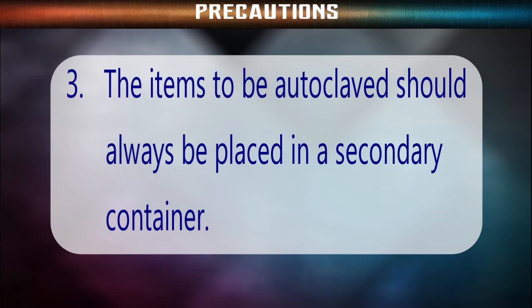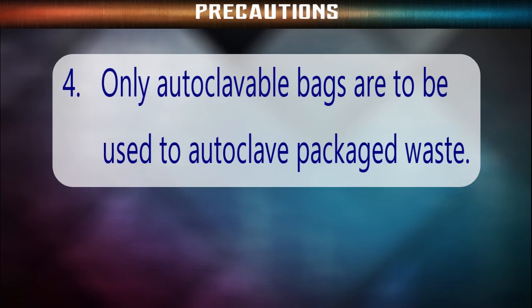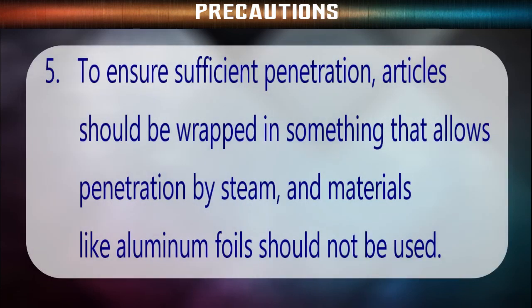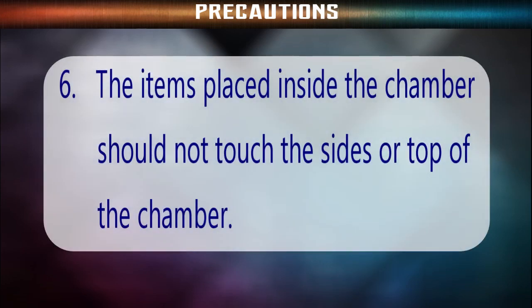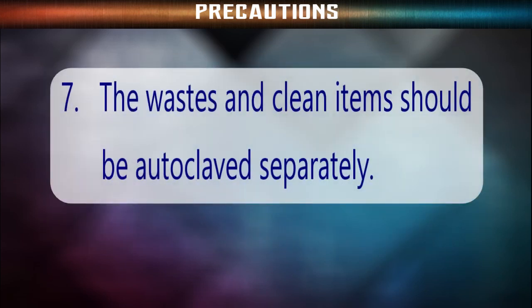The item to be autoclaved should always be placed in a secondary container. Only autoclavable bags are to be used to autoclave packaged waste. To ensure sufficient penetration, articles should be wrapped in something that allows the penetration of steam, and materials like aluminum foil should not be used. The items placed inside the chamber should not touch the side or the top of the chamber. The waste and clean items should be autoclaved separately.